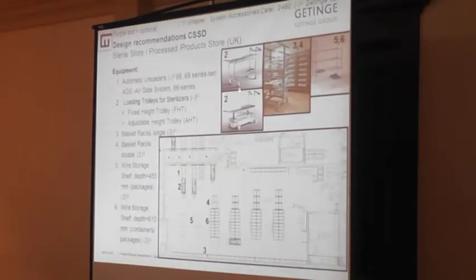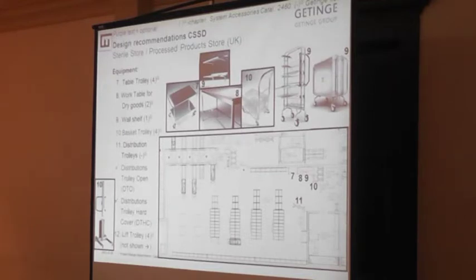The items we use are, of course, the sterilizer trolley that we load out from the sterilizers, the basket rack that we mentioned, the baskets, and the wire shelf with the containers. And when we're going to assemble, we get the order from the operation. We're going to have a hip surgery, for example. Then we need to find the items somewhere here in the sterile store. We have an assembly table that we see here. And then we take a simple trolley, and we go and pick up the items for that actual surgery. And we assemble that on the table here. Put it on a trolley, open trolley or closed trolley. And then we bring it out just in time for the next operation.